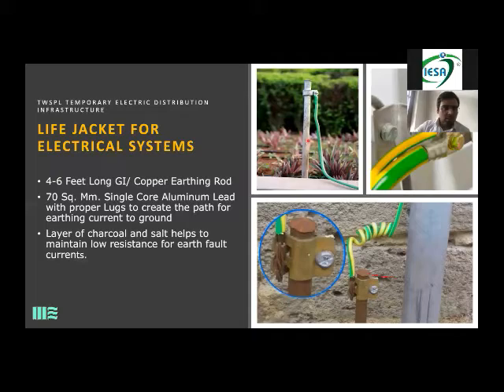It just depends from site to site, on how long you have the site. If you're having the site only for maybe a day or 2 days, and then your event is on the third day or so, this type of earthing works. It is not bad. It is not necessary that every time you have to put koila, namak. You can use these rods depending on the soil where you're working. The earthing needs to have less resistance. That is what we are trying to create.